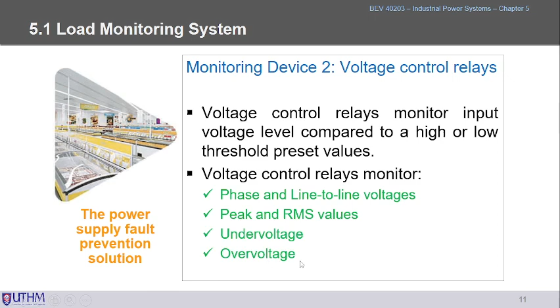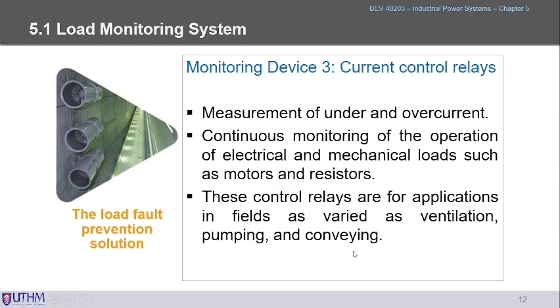So our intention is to monitor and control the currents. It's not like the incoming power supply, where we are concerned more with the voltage quality. At the load side, the current will be our priority. So at the load level we can use current control relays to detect under-current or over-current issues. They continuously monitor the operation of electrical and mechanical loads, and are applicable in fields as varied as ventilation, for example a pump or a conveyor.